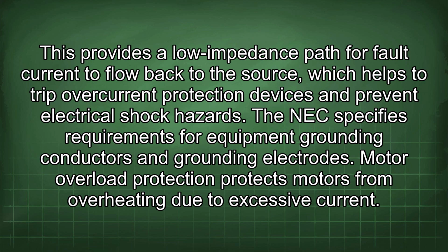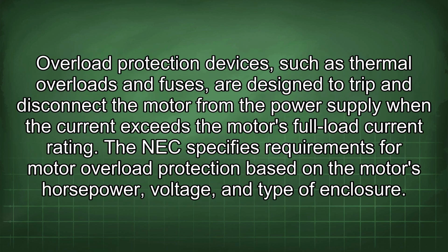Motor overload protection protects motors from overheating due to excessive current. Overload protection devices, such as thermal overloads and fuses, are designed to trip and disconnect the motor from the power supply when the current exceeds the motor's full load current rating. The NEC specifies requirements for motor overload protection based on the motor's horsepower, voltage, and type of enclosure.